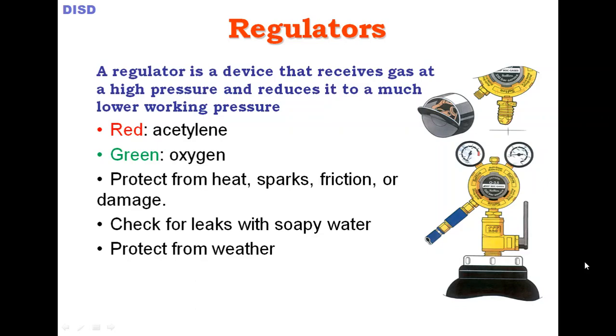After the regulator is attached, the cylinder valve should be opened just enough to indicate pressure on the regulator gauge, and all connections should be checked with a soap solution for leaks. Gradually open the valve and check that the regulator gauge meter is working properly. Before the regulator is removed from the cylinder, the cylinder valve must be closed and the cylinder cleaned and returned to the storage area.